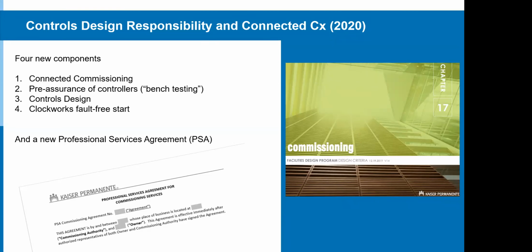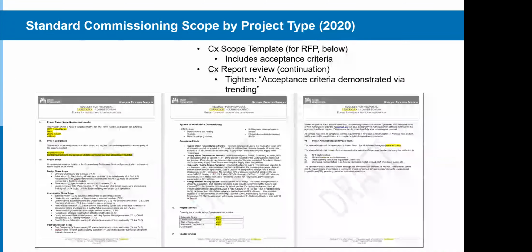We did have to rewrite our professional service agreements for commissioning agents there. We also, starting in 2020, required connected commissioning for projects. So when we're doing trending, it's no longer acceptable to email spreadsheets of trend data back and forth. You have to have a connected commissioning program where you're looking at data real time and doing data analytics real time.